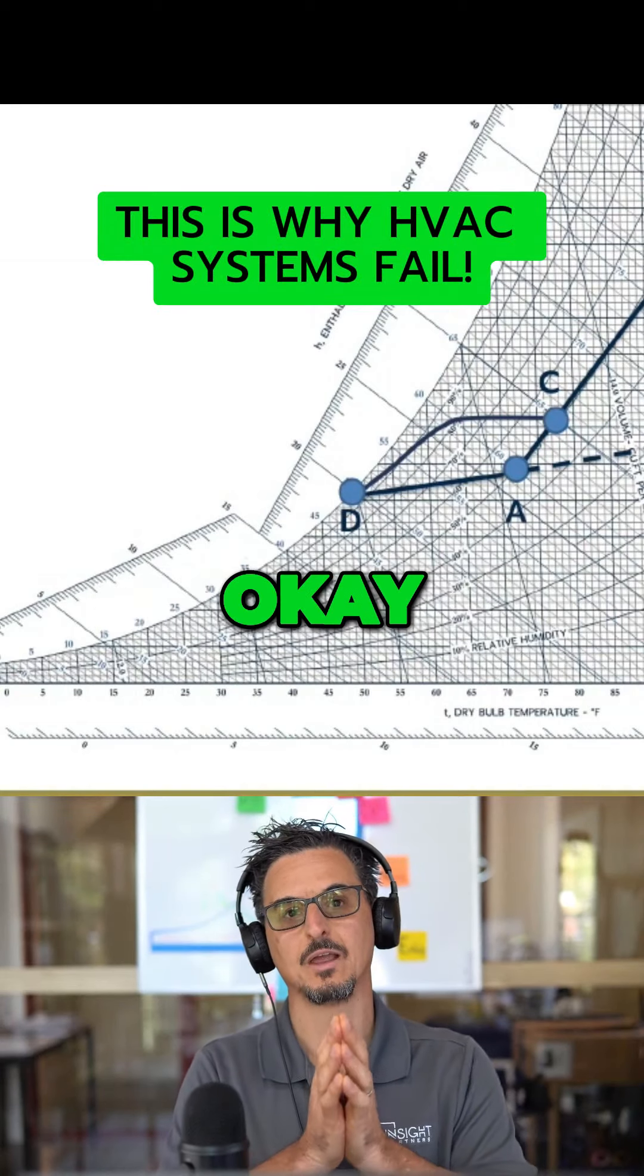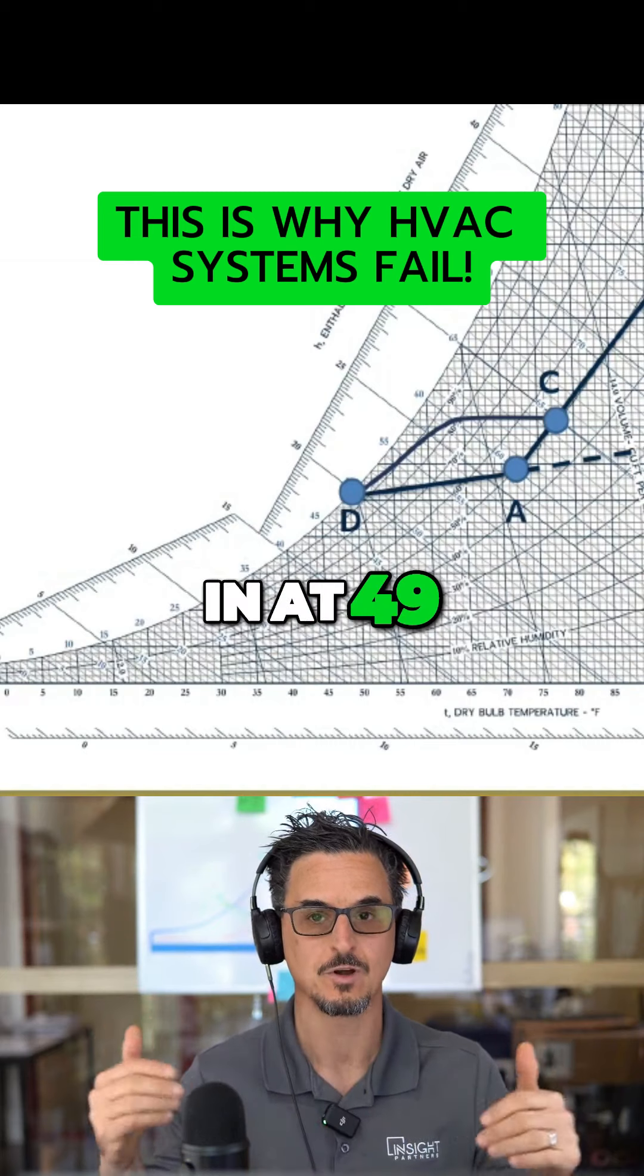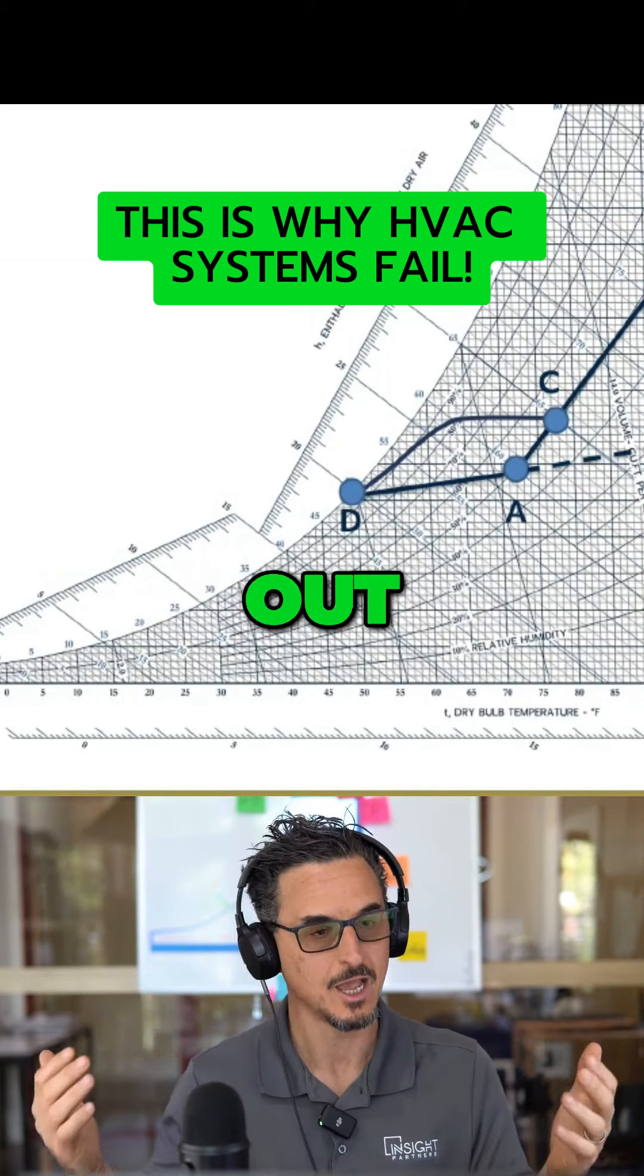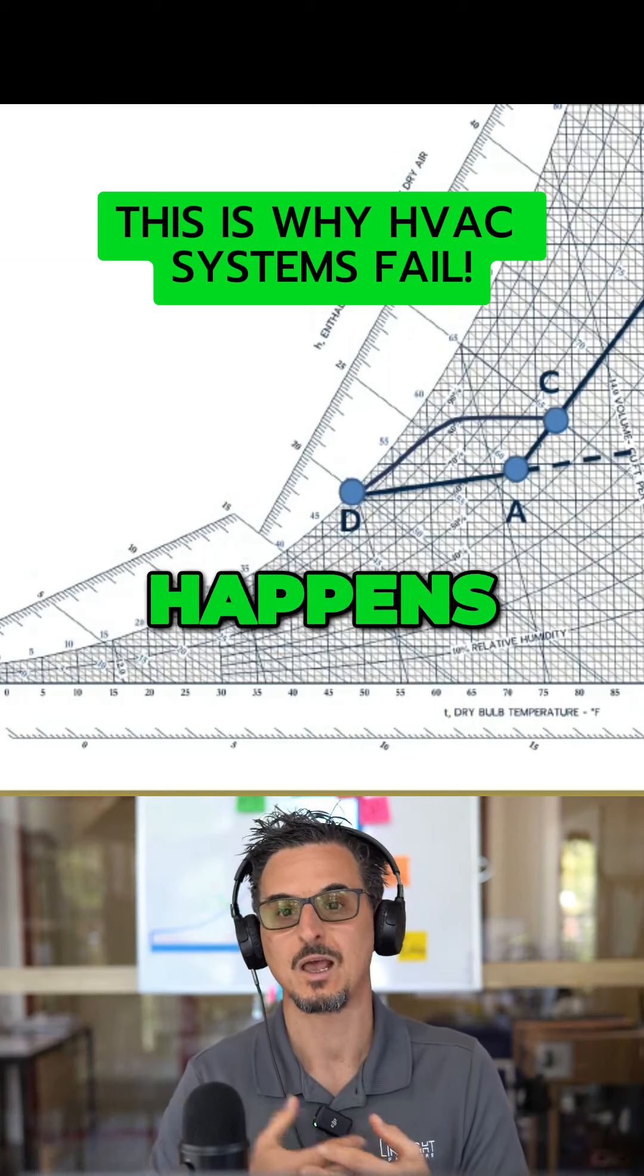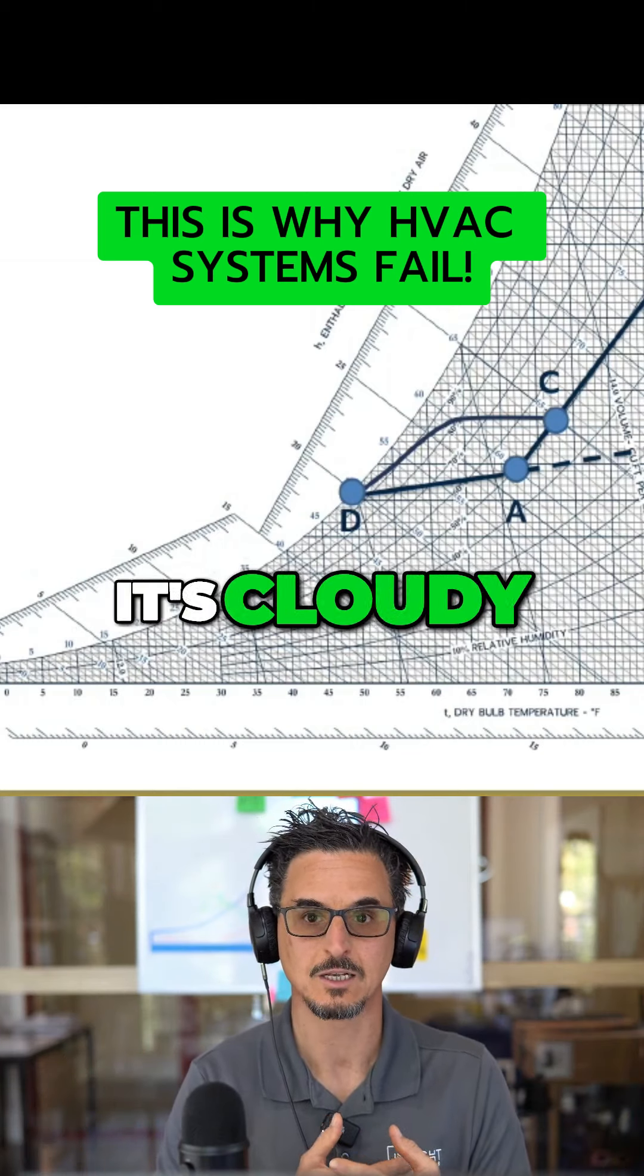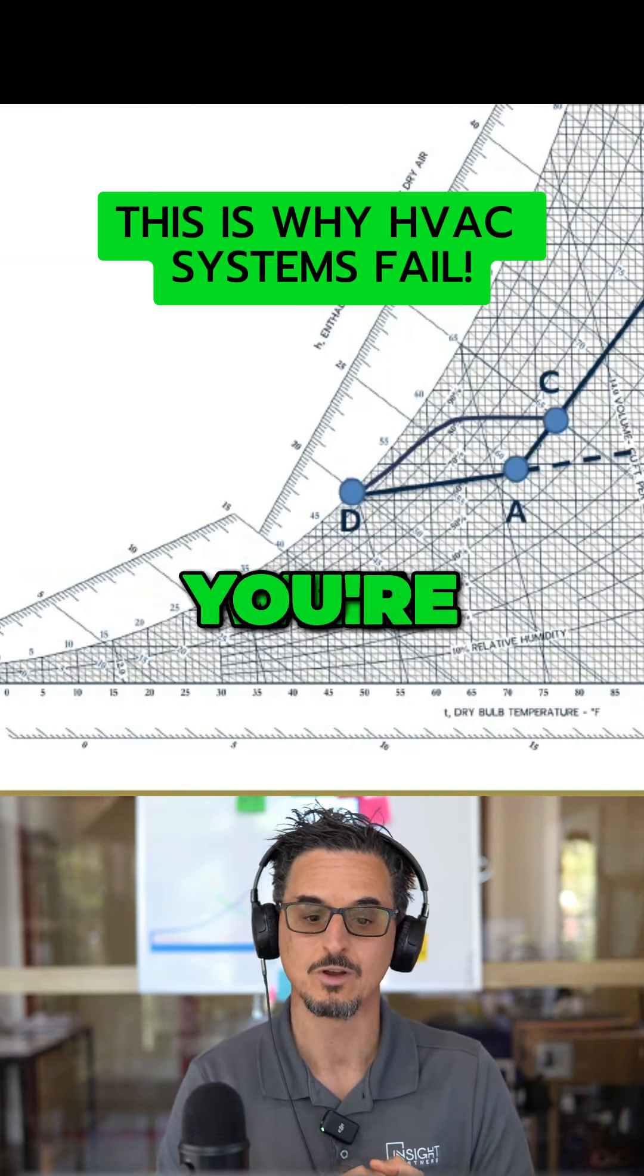So what happens in the real world? You're in the space, 3200 CFM is coming in at 49 degrees. It's sunny out, it's hot, it's fully loaded, everybody's fine. What happens on the day when it's cooler outside, it's cloudy, there's not as many people in there, and it's still providing 49 degrees? Well, you're going to over-cool the space, right?